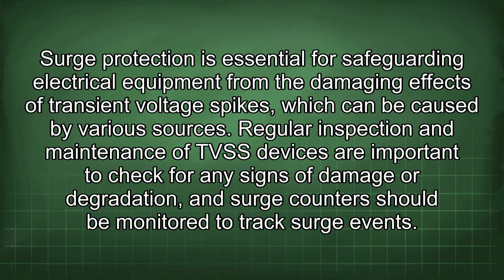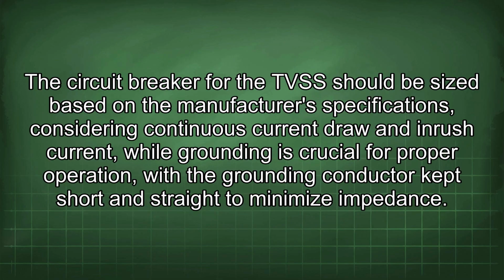degradation, and surge counters should be monitored to track surge events. The circuit breaker for the TVSS should be sized based on the manufacturer's specifications, considering continuous current draw and inrush current, while grounding is crucial for proper operation, with the grounding conductor kept short and straight to minimize impedance.